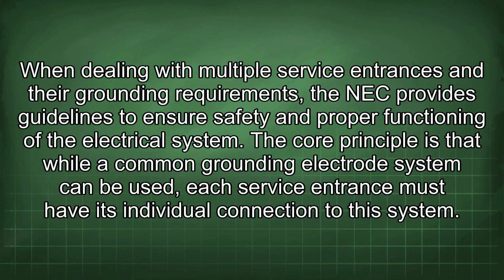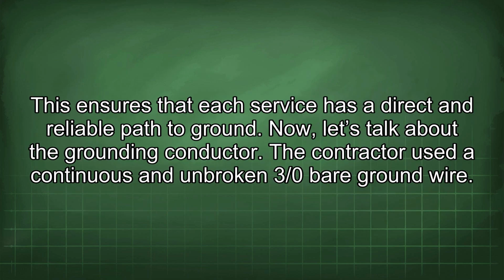When dealing with multiple service entrances and their grounding requirements, the NEC provides guidelines to ensure safety and proper functioning of the electrical system. The core principle is that while a common grounding electrode system can be used, each service entrance must have its individual connection to the system. This ensures that each service has a direct and reliable path to ground.